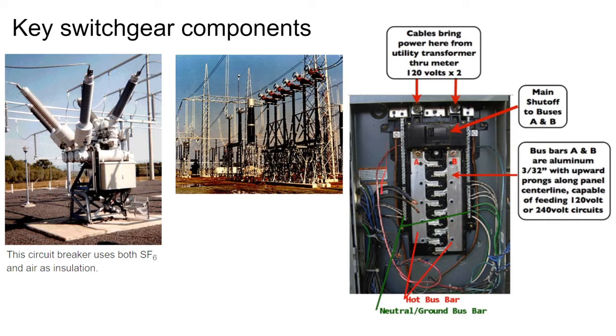Generally, where should the power be coming in on this panel? Usually it's a little obvious. The power's coming in up here and all the work is being done down here. This allows an electrician to kill the main breaker, and this side of the panel is still live, but they can work on the underside of the panel without it being a safety hazard.